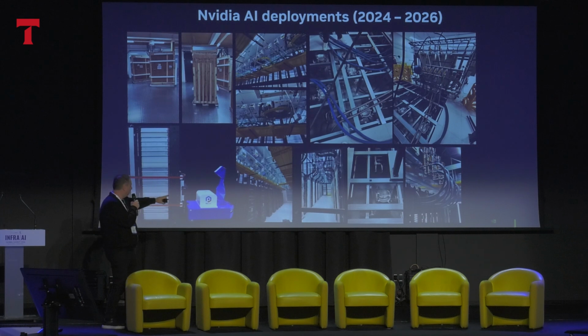And then in order to push these racks, we are using what we call the server tug. Basically you need to push the rack to the final position. Right now, the current racks have 4 casters, the new racks will have 6, and if the rack is going above a certain limit, you will need a small forklift to bring it to the final location, because the casters will not be able to hold the weight.